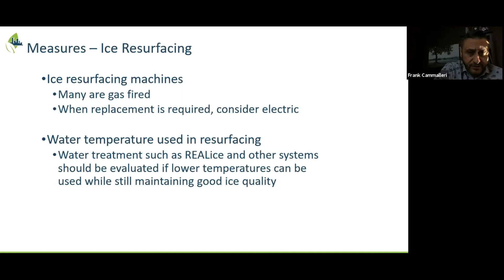Water temperature is another big factor affecting refrigeration load. We found ice resurfacing water temperatures varying by facility, as low as 120-130 degrees, as high as 160-170. So there's an opportunity to reduce that temperature. There are systems out there like REALice, and we'll be investigating others, or just in general reducing the temperature while maintaining the ice quality people expect. Lowering the water temperature used in resurfacing tends to result in a reduction in refrigeration load, all while maintaining good ice quality. That goal stays at the forefront—you need to maintain quality to provide a continuous surface in the rink.